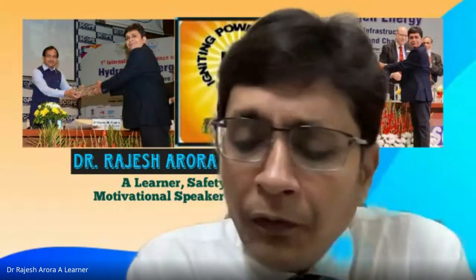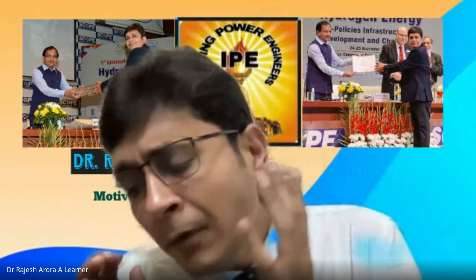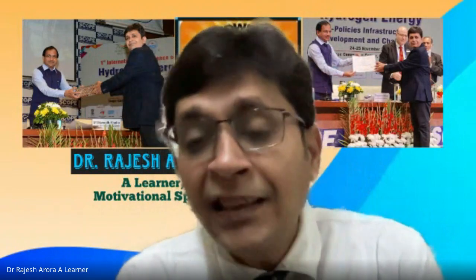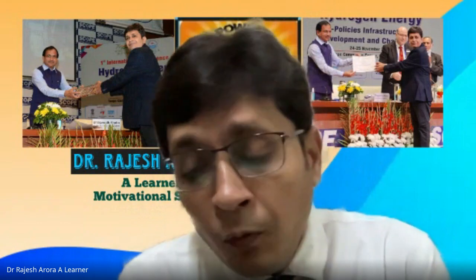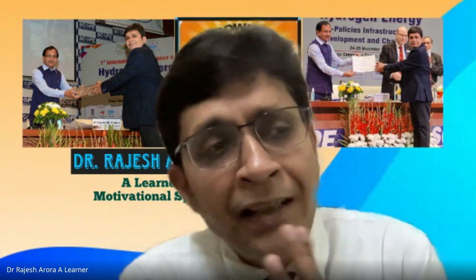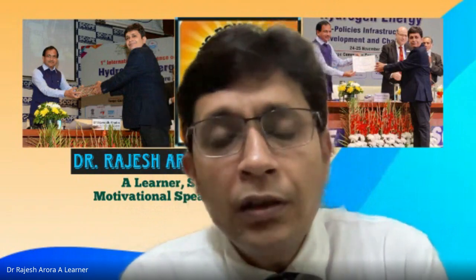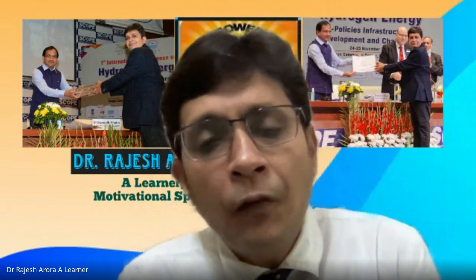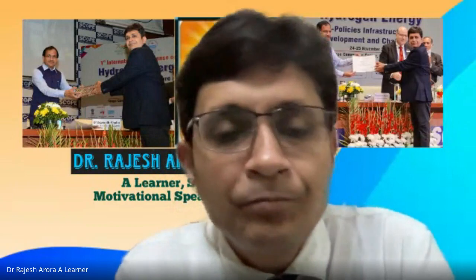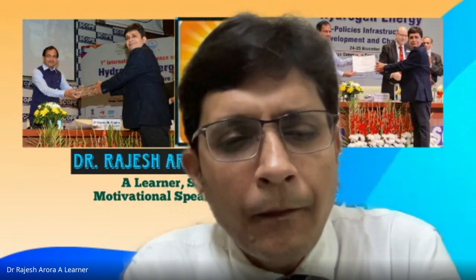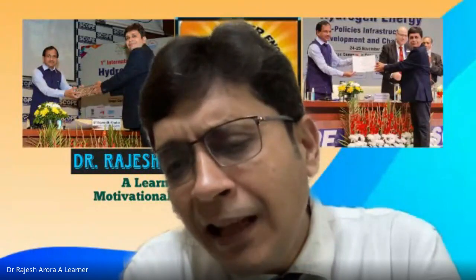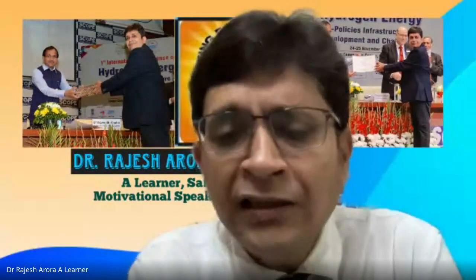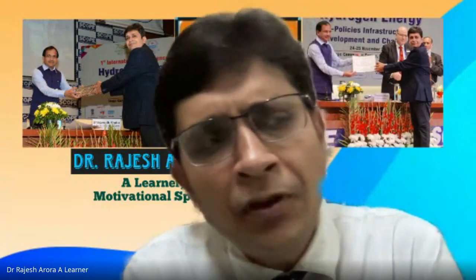But whenever you are stuck in lightning, you have to be very careful. You have to take your steps wisely. You should not run. You have to move with very small steps. You should not touch any metallic object. That is the only possible way to get out of a lightning attack on the human body. Cases have increased, sir. A few years back, it was not like that. Actually, when people die in lightning, it is because of ESP, as I have already mentioned, Earth Surface Potential, and that leads to touch and step potential.